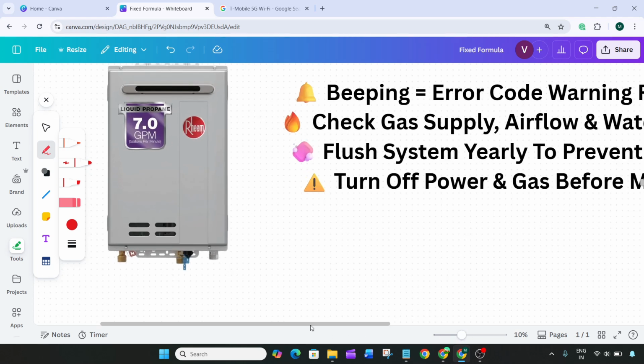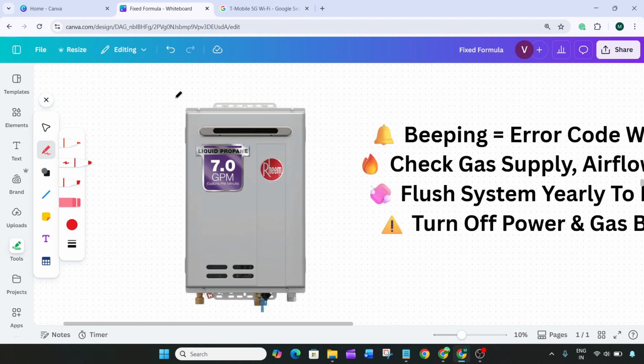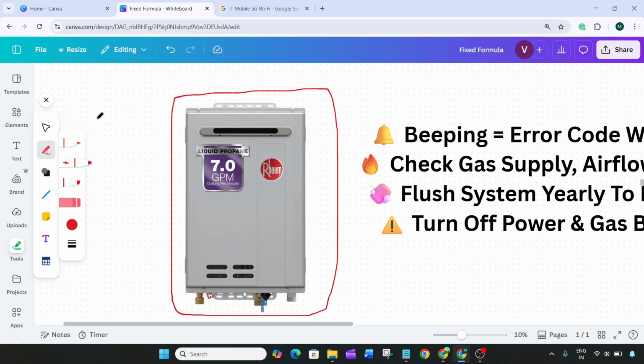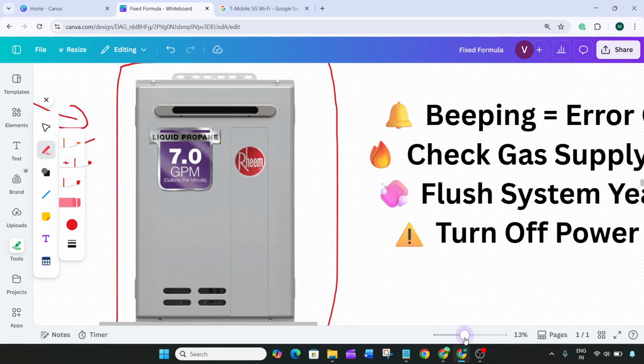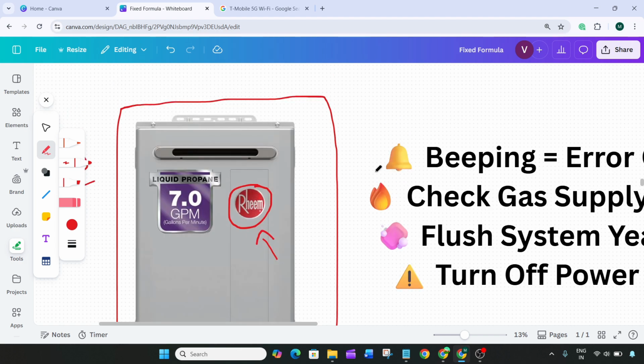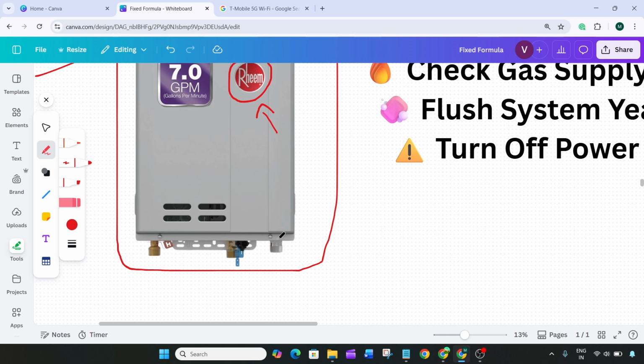If your Rheem tankless water heater starts beeping, it usually means the system has detected a problem and is alerting you through an error code shown on the display or remote panel. These codes help identify exactly what's going wrong so you can troubleshoot faster. For example, code 11 normally points to an ignition failure, often caused by gas supply issues or a faulty igniter, while code 12 means flame failure, where the unit cannot properly detect combustion.